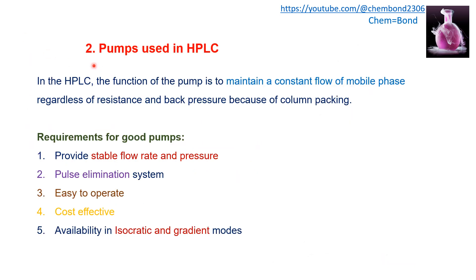The second component of HPLC instrumentation is pumps. The mobile phase carries the solute molecules through the column and passes towards the detector. The close packing of the HPLC column creates resistance in the mobile phase flow as well as back pressure. In HPLC, the function of the pump is to maintain a constant flow of mobile phase regardless of resistance and back pressure created due to column packing.